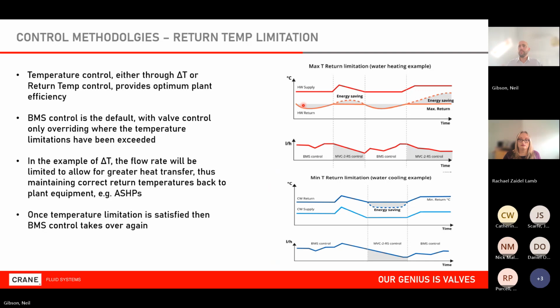So how does that work? Let's take the example up here in a heating system. So I've got my supply temperature, slight variation there, and I've got my return temperature based on these T1, T2 sensors. If I set a limit, you can see that's this line going along here. If I set a limit, the system will ensure that as the temperature was due to creep back up, so my delta T would be poor, the valve will take over control from the BMS and reduce the flow rate. And it will reduce the flow rate to create a better heat transfer to maintain that return temperature, or at least so it doesn't go above the limit. And it'll do it automatically. All I have to do is set what that value is.